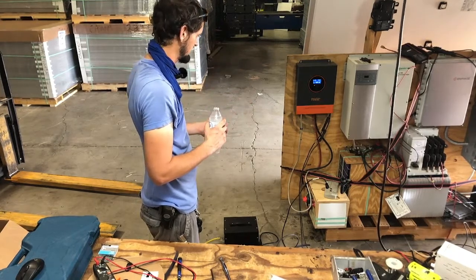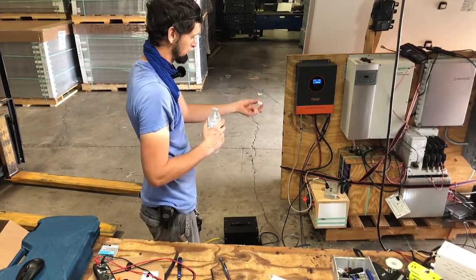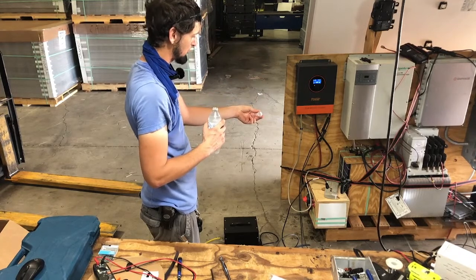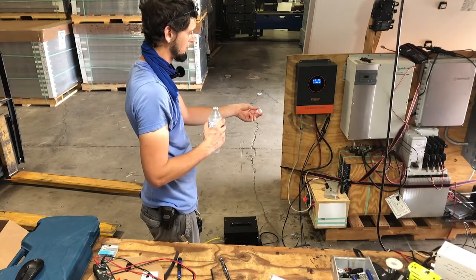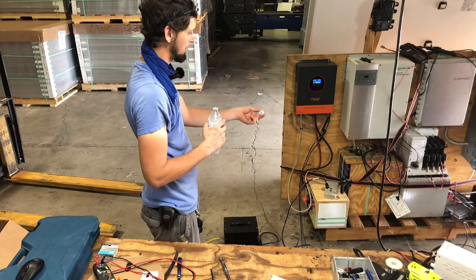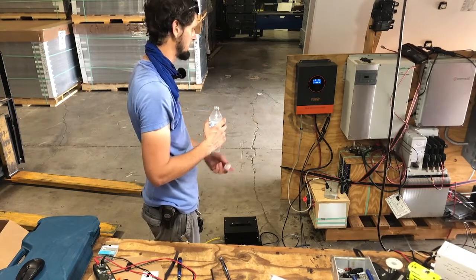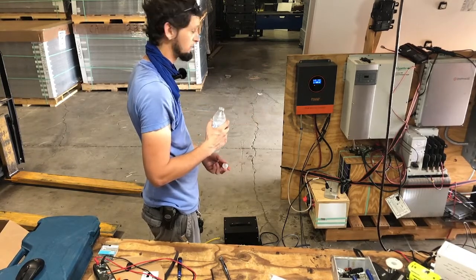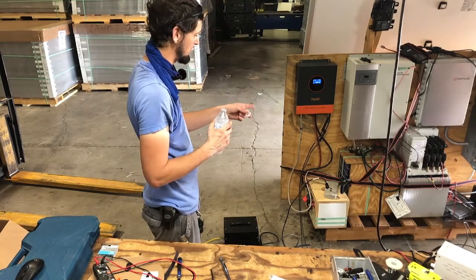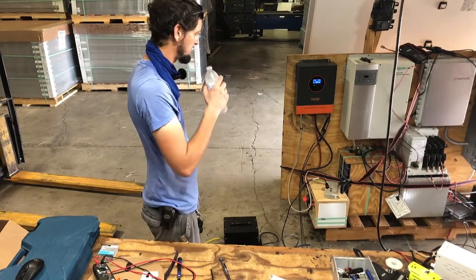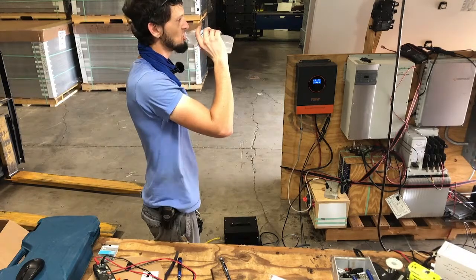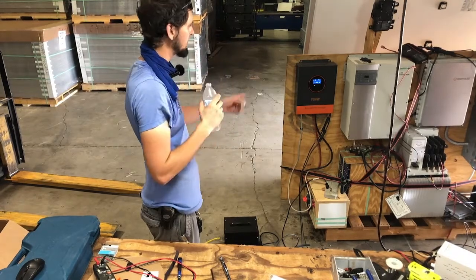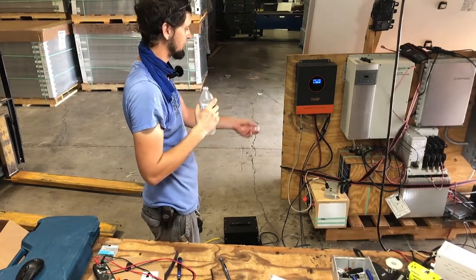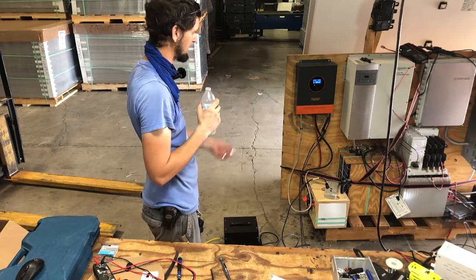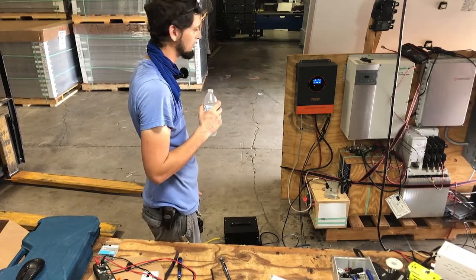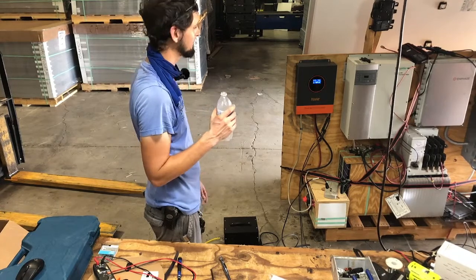Just used a power strip, which, assuming that power strip actually has a circuit breaker in it, that's going to trip at 15 or 20 amps, 15 amps. It's relatively safe, the wire between, yeah, I mean that's... you're never going to get the full 3,000 watts out of it because it's a power strip that can only do 15 amps, and that thing can push out like 25. That thing can provide 25.